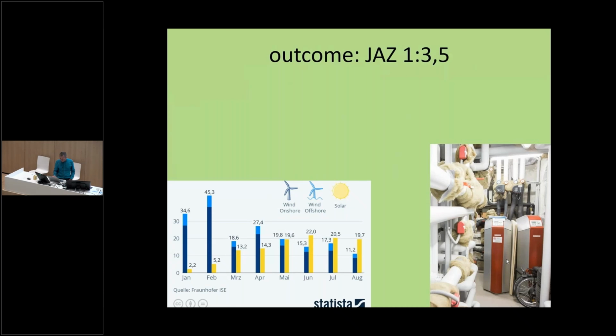So that's what the outcome is at the end, or is it COP? COP is 3.5. You can see the heat pumps here. The small one has 5 kilowatts and brings out 20 kilowatts, and this is 10 and brings out 40 kilowatts. This is for heating, this is for warm water, but they can help each other, and this is the sheep wool on all the not insulated parts.